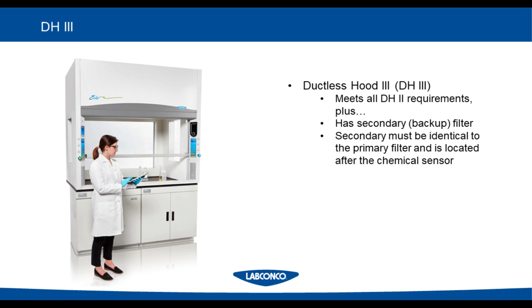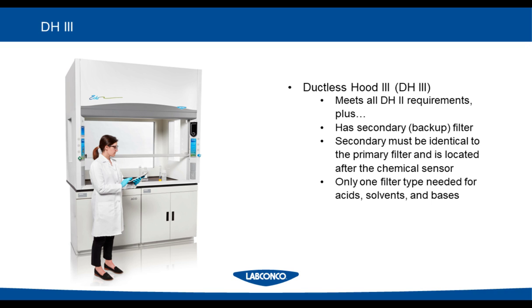With the DH3, it has a secondary filter. So even if that alarm goes off, you still have your secondary backup filter that will protect you for as long as it takes to decontaminate the hood or just get everything out, and then ultimately replace the filters. These filters are of one kind, and they're built to handle acids, solvents, and bases. So again, the difference here between the DH3 and the DH2 is that the DH3 offers a new dimension of versatility in that you don't need to buy multiple types of filters. You're good with the one, which is a big benefit.